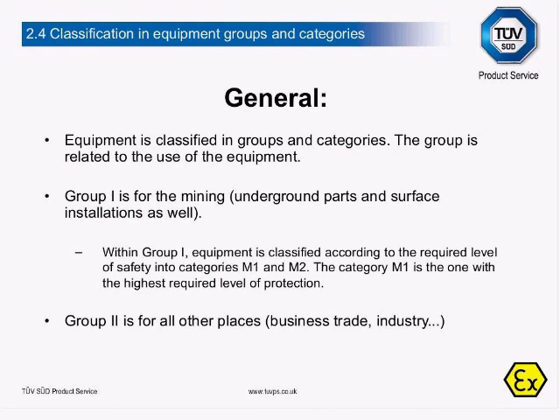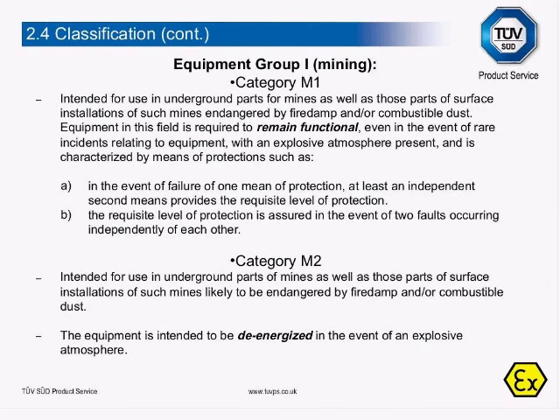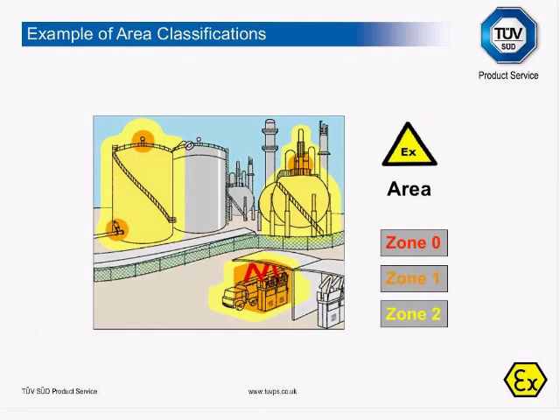Equipment is classified in groups and categories. The group is related to the use of the equipment. Group 1 is for mining — underground parts and surface installations. Group 2 is for other places: business, trade, etc. Equipment Group 1 for mining is detailed in two categories: Category M1 and Category M2. Here we can see a typical example of a hazardous area classification overview schematic showing different areas — Zone 0, Zone 1, Zone 2 for gases — noting the different types of symbol: the EX sign for the area and the EX symbol for the component or equipment.